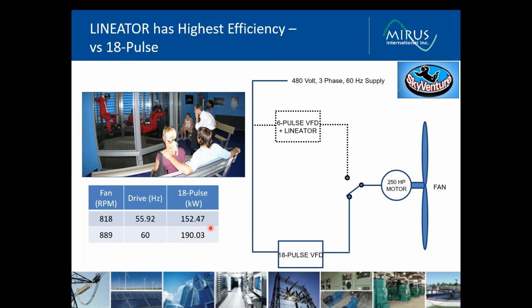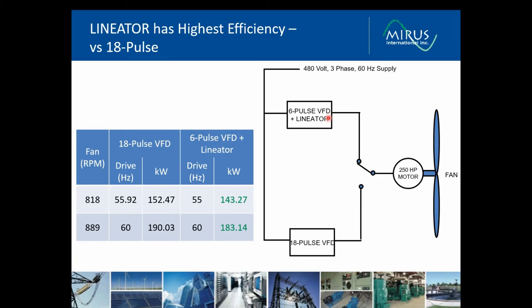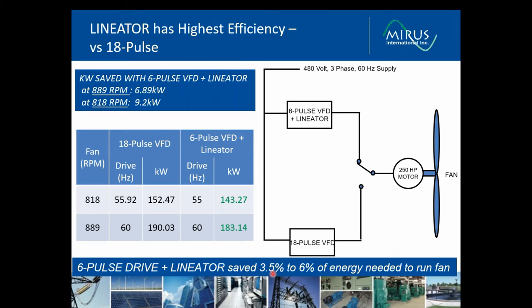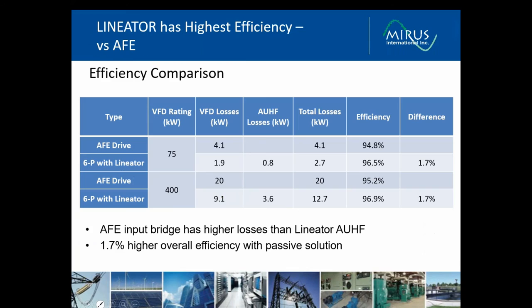So they ran the system using the 18-pulse competitor's drive, and at full fan speed at 60 hertz, they were drawing 190 kilowatts. With the reduced speed, just under 56 hertz, the system was drawing 152 kilowatts. When they switched to their drive with a 6-pulse filter, at full speed, the system was only drawing 183 kilowatts. And at the reduced fan speed of 818 RPM, they only needed to run the drives at 55 hertz. So the filter was improving the operation, allowed them to go at a lower speed, which reduced the kilowatt consumption even further. So at full load operation, there was a 3.5% reduction in real power. At the lighter load operation, there was a 6% reduction. So real energy savings associated with those two systems.